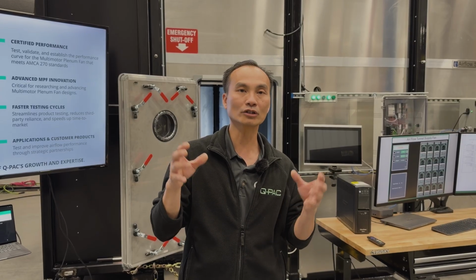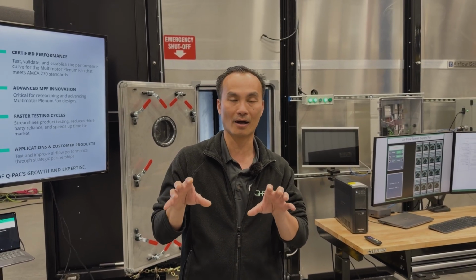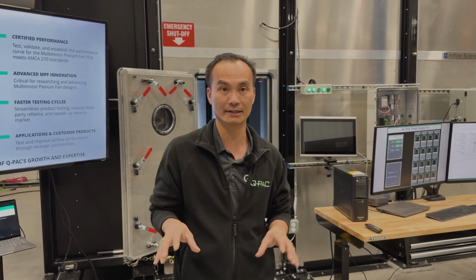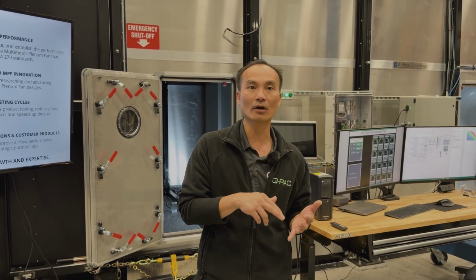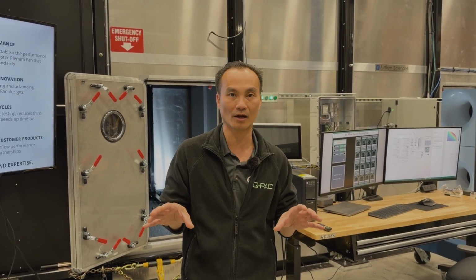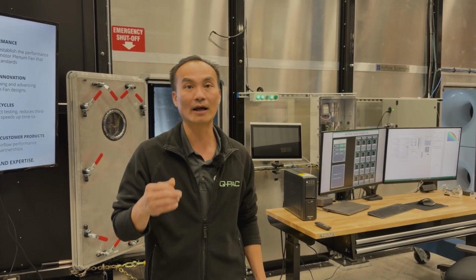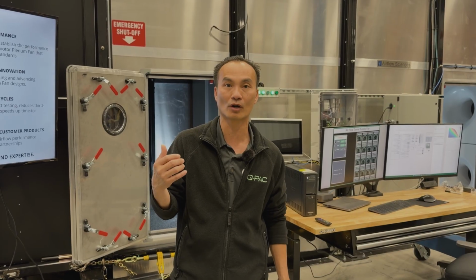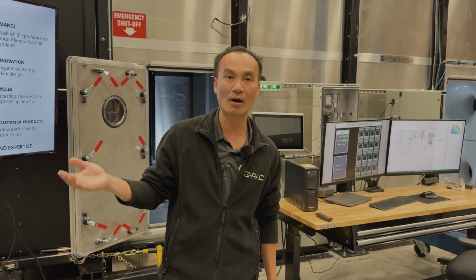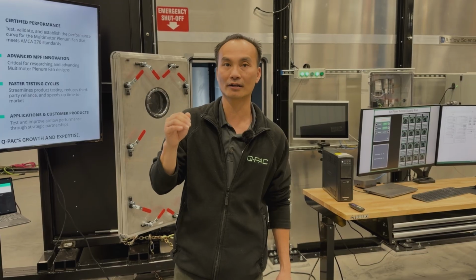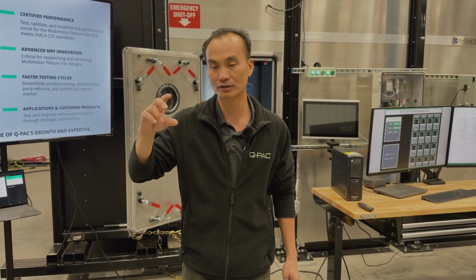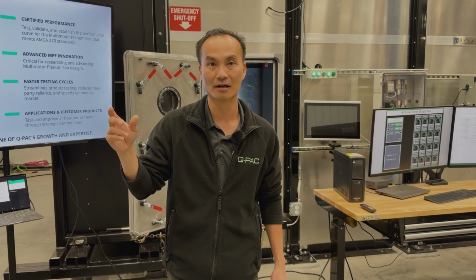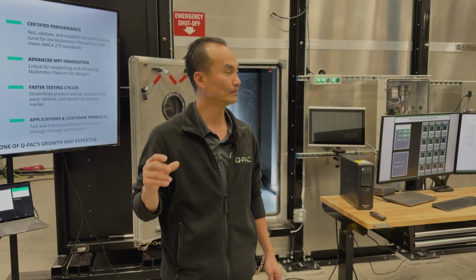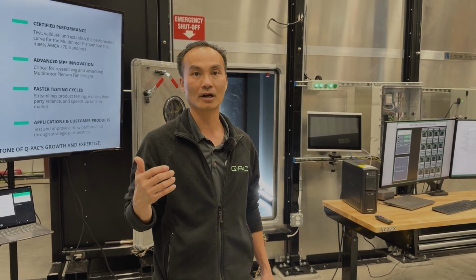Without the AMCA 270, if you put multiple fans together today, most of the data you can see from any fan design or multiple fan array design is an estimation, because they don't have any capability to test multiple fans together with a dynamic effect or at the system effect. So that is required to put the AMCA 270 stamp onto the product. That also shows our customer that the design of our product is actually accurate, not just by extrapolation, not just by expected data, but it's real data. It's a real performance. That is why the AMCA 270 is so important, because that's required by the industry.